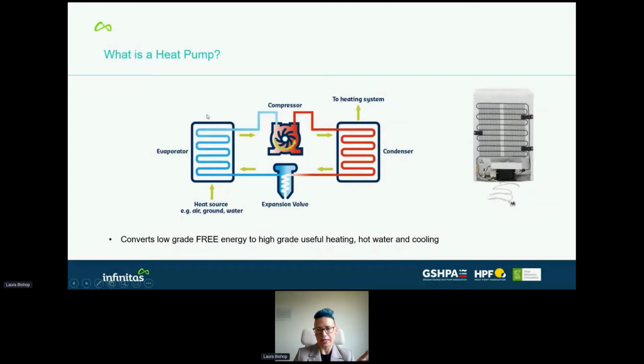So to start with, let's have a look at what a heat pump is. Essentially we're talking about vapor compression heat pumps, rather than any other kind of heat pump. They're the most popular ones used in Britain today. We have 4 items: 2 heat exchangers called an evaporator and a condenser. The evaporator is the cold side, the condenser is the hot side. We have an expansion valve to allow refrigerant to expand, and a compressor, which is the electrical piece of kit.